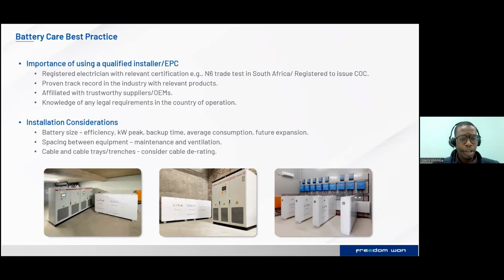So in some instances, you do find installers with a higher rated inverter and a lower rated battery, and the battery is not spec'd correctly to cater for the continuous or the peak demand. So it's very critical to ensure that the battery is sized correctly and is not undersized for that particular inverter. Normally, suppliers or OEMs specify the maximum kVA of an inverter that a battery needs to be connected to. Those things need to be adhered to, to ensure best practices.